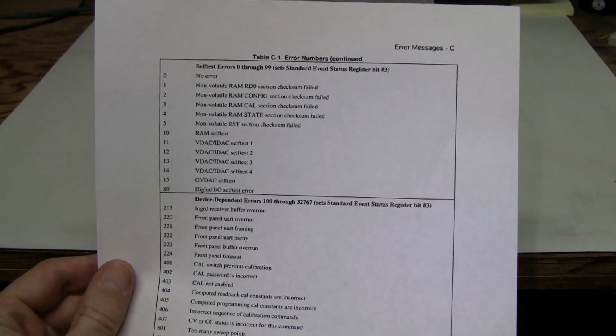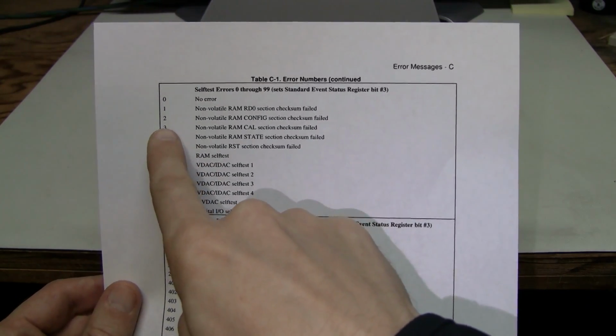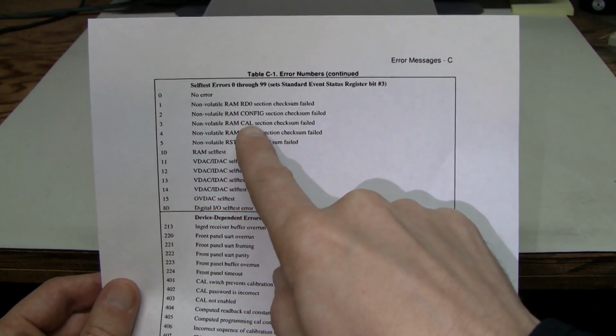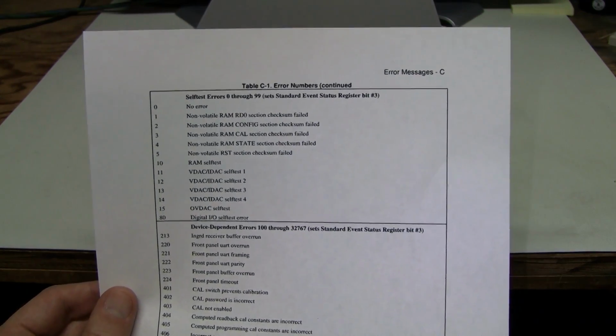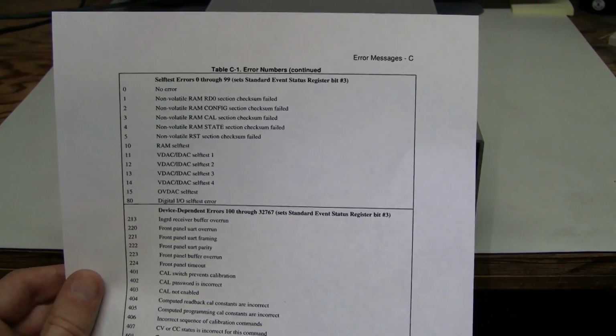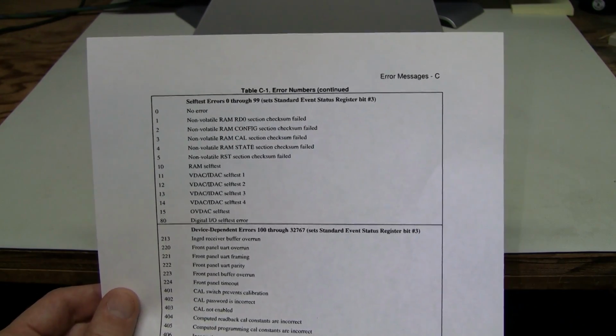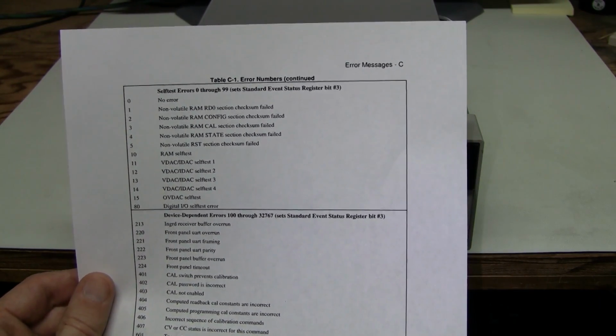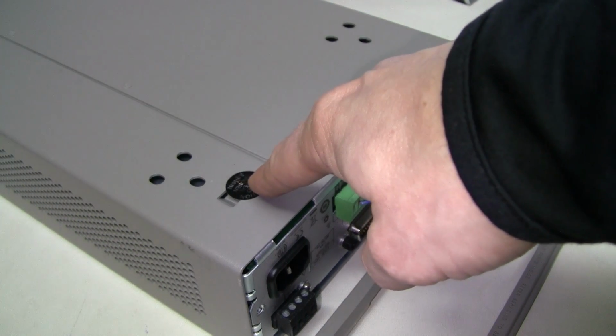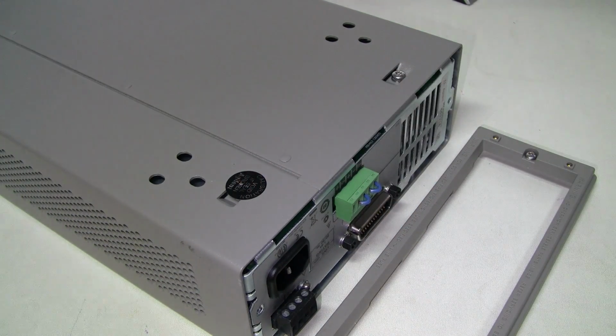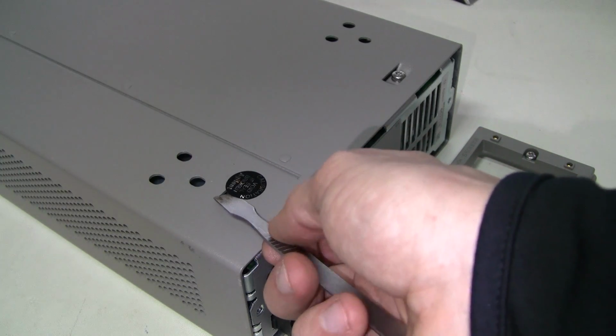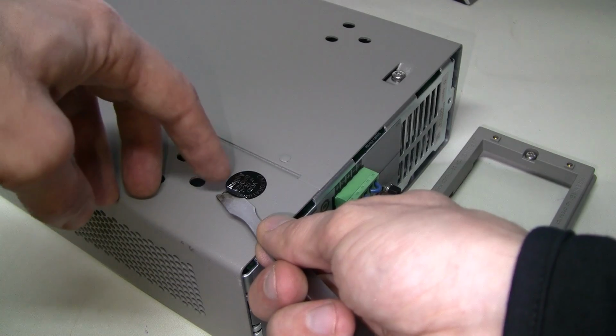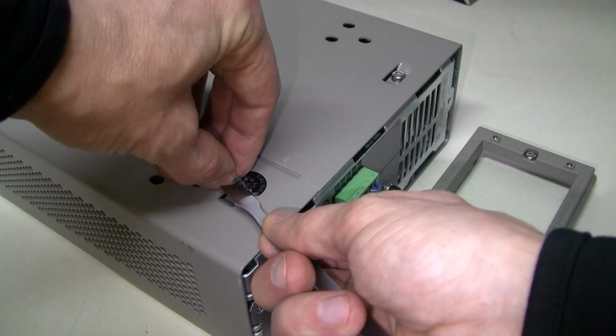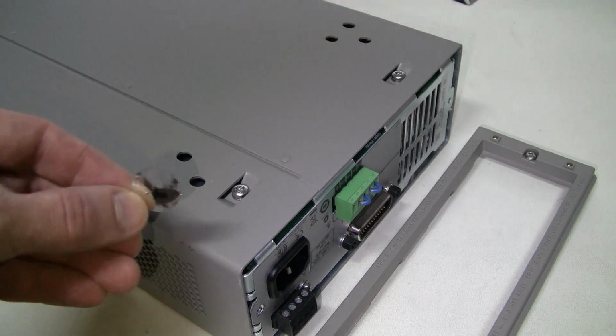Here I found error messages in the user manual, and the error three is non-volatile RAM cal section checksum failed. I wonder, is it related to the protection thing at all, or maybe these are 2 different problems? One of the bolts on the bottom of the unit is covered with Agilent calibration sticker. Let's see if I can carefully remove it. No worries.